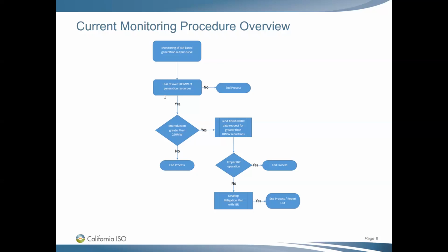And then we ask: is it because of an IBR reduction that is greater than 250 megawatt? So right now we are looking at whether there is an IBR reduction of greater than 250 megawatt on the event that is 500 megawatt. And then we would send data requests for each of the IBR that has a reduction greater than 10 megawatt. So that's the sequence.